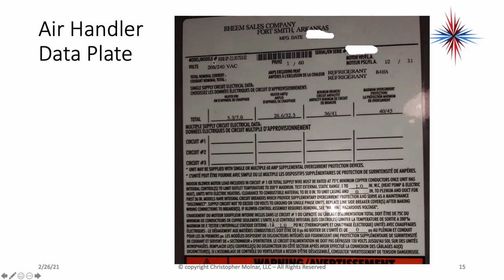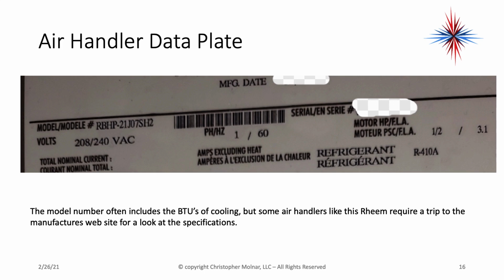You look at the data plate of the air handler. There's a lot of information on here that we use to calculate airflows. Let me point out a few things. First of all, the model number includes the BTU of cooling a lot of times, but on some air handlers like this Rheem, it requires a trip to the manufacturer's website to look at the specification.